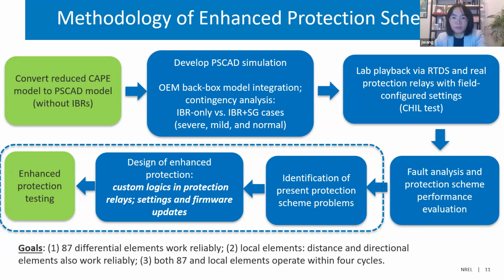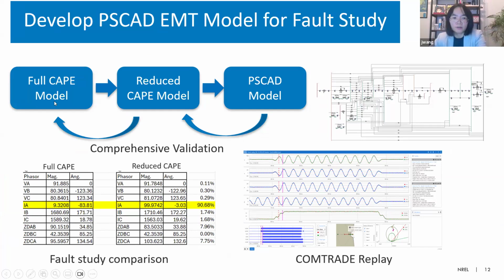So this is the methodology of our study, and the slide here shows our process to get the PSCAD model. We actually start from the full CAPE model, and then we did the reduction to include only the area of interest, and then we further develop the PSCAD model. For each model reduction and development, we go through a fault study comparison. So we run through single line fault, double line fault, and single phase ground fault to see if the current levels match or not. We also run through the trace data and replay it in the relay and then see if the relay response matches with the previous model. So after this comprehensive validation, we finally get a good PSCAD model that we can use for the simulation for the fault study.